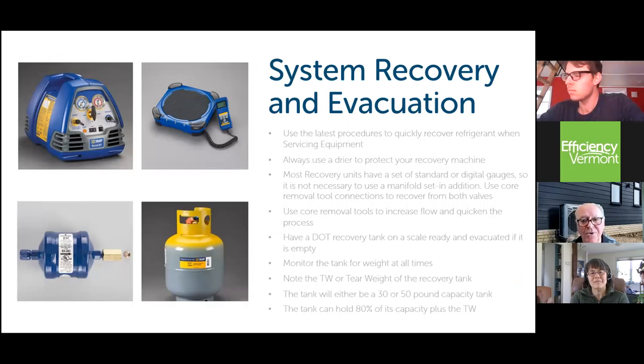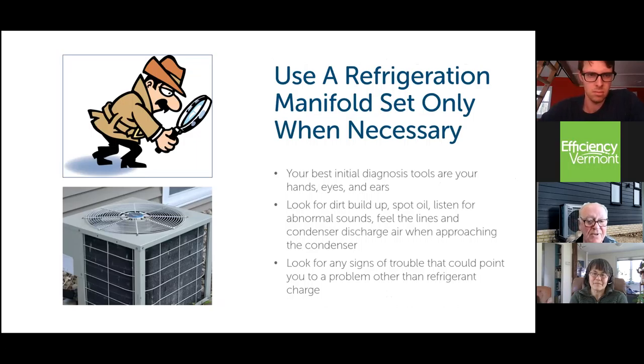But your best initial diagnosis tools are your hands, eyes, and your ears. You look for dirt buildup and oil spots, because where refrigerant is leaking, you're going to find dirt in the area. Pressure, refrigerant, and dirt will mix, and you're going to find an oil spot. Listen for abnormal sounds. All these things you can do without putting a manifold on a system.